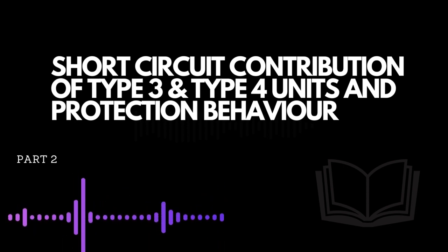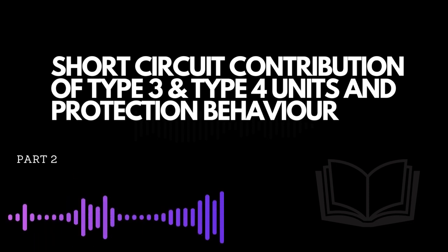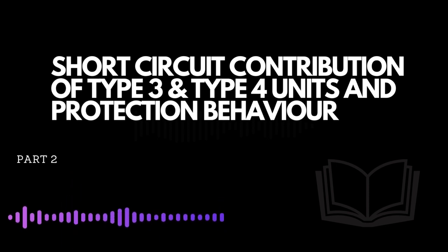Faulty phase selection. As explained in previous chapters, the crowbar action is affecting the short-circuit current contribution from DFIG generators. Algorithms based on superimposed quantities can be affected due to the current waveforms in case of multiple switching of the crowbar. Then, errors in faulty phase selection could be expected if superimposed quantities algorithms are implemented. As DFIG generators under unbalanced faults inject negative sequence currents, algorithms based on negative sequence are expected to present good behavior even in case of multiple switching of the crowbar. Current-based algorithms are expected to be affected under unbalanced faults.